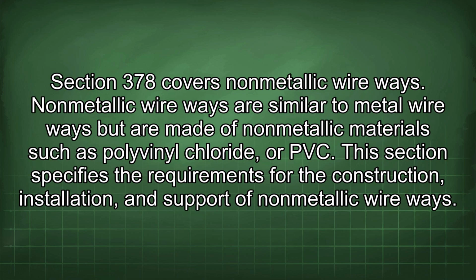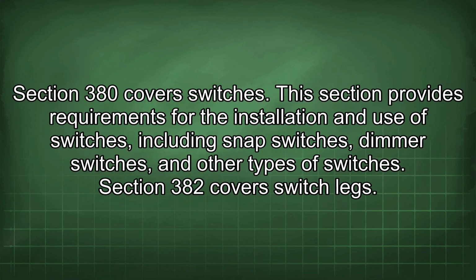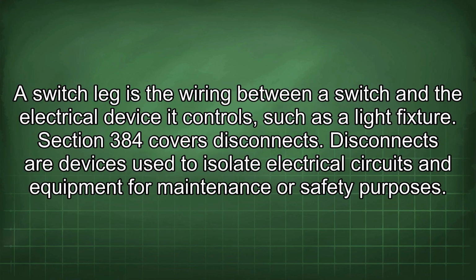Section 378 covers non-metallic wireways. Non-metallic wireways are similar to metal wireways but are made of non-metallic materials such as polyvinyl chloride, or PVC. This section specifies the requirements for the construction, installation, and support of non-metallic wireways. Section 380 covers switches. This section provides requirements for the installation and use of switches, including snap switches, dimmer switches, and other types of switches. Section 382 covers switch legs. A switch leg is the wiring between a switch and the electrical device it controls, such as a light fixture.